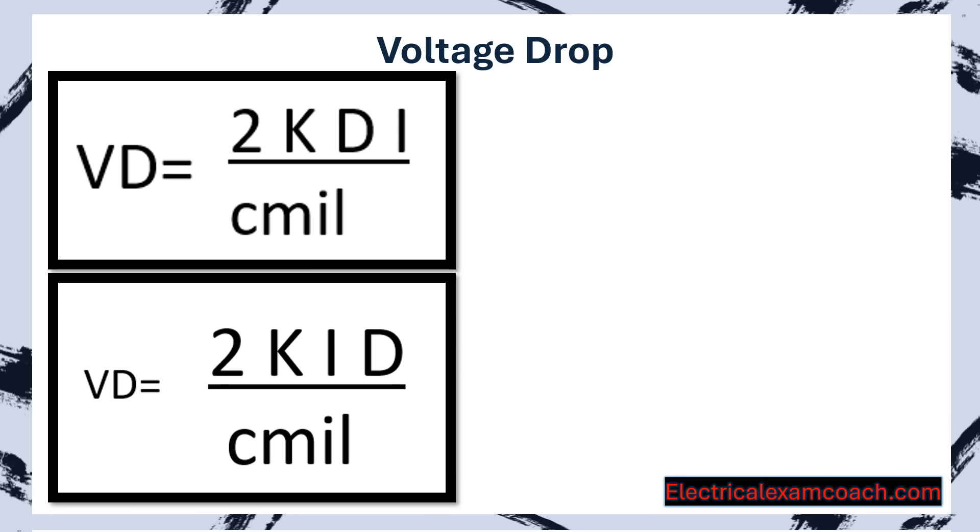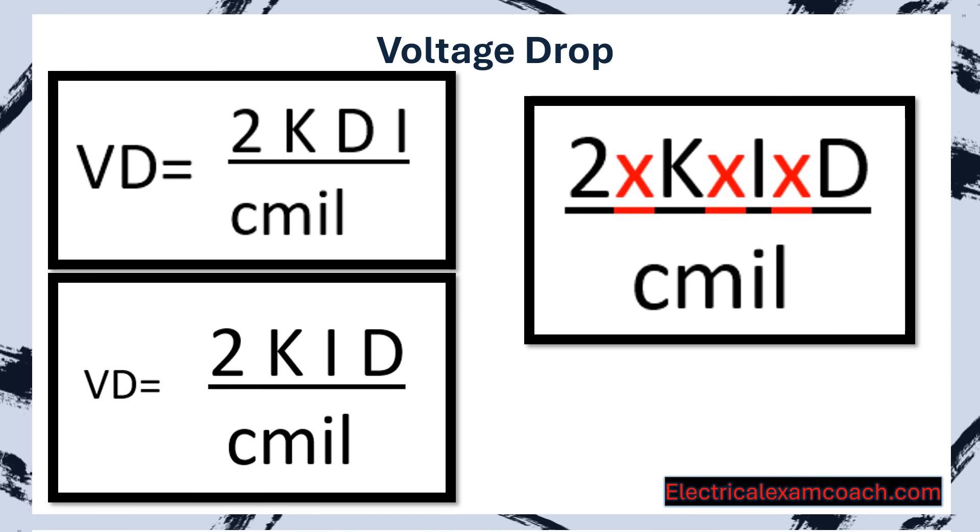I do it like this: 2KID over cmil. Easy to remember and easy to plug in. What this is, just like previously in the program, is implied multiplication. So it's going to be 2 multiplied by K multiplied by I multiplied by D divided by cmils. Now let's learn what each one of these individual pieces mean.